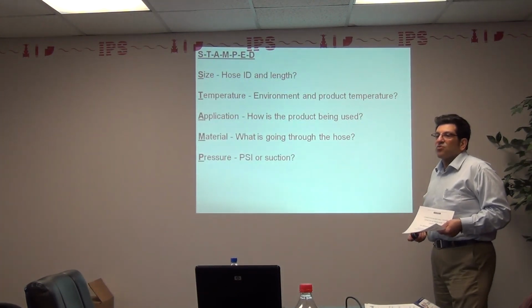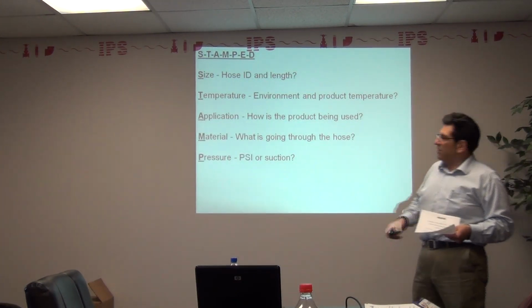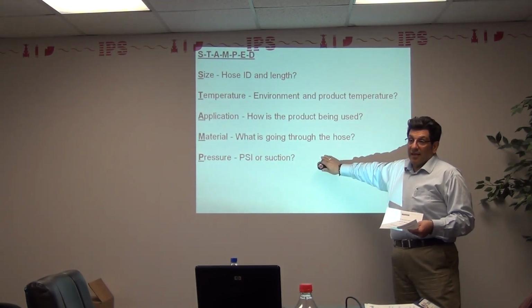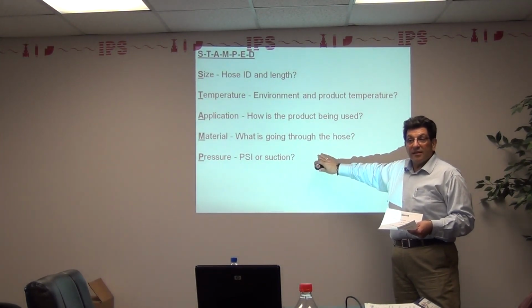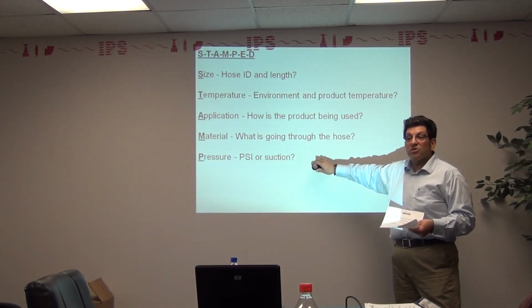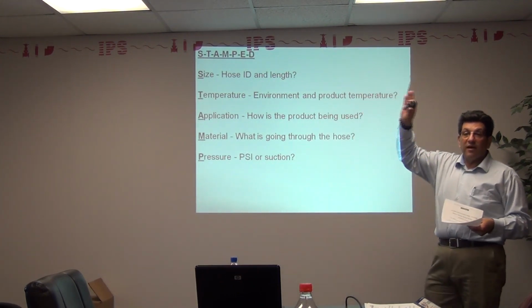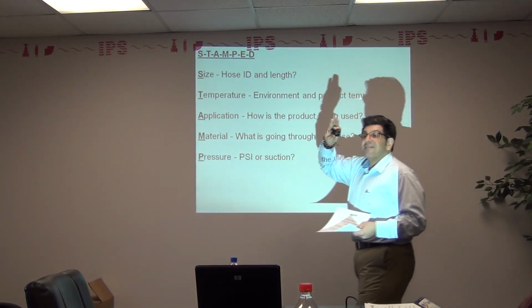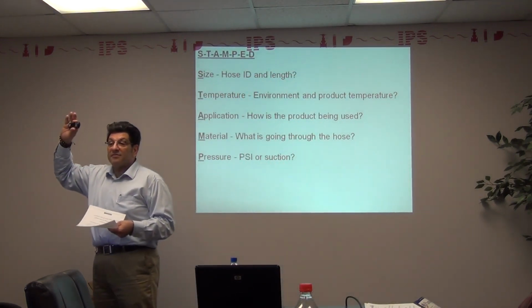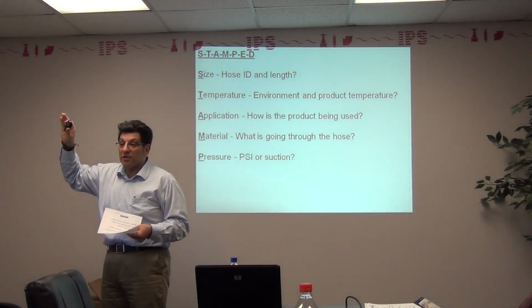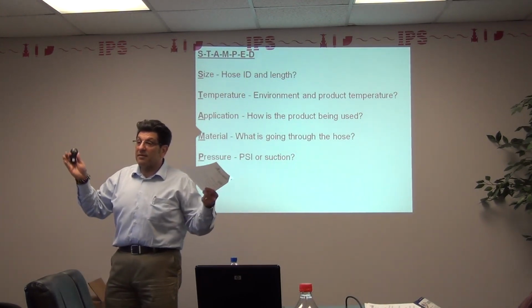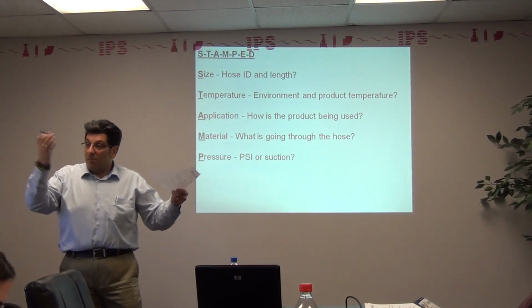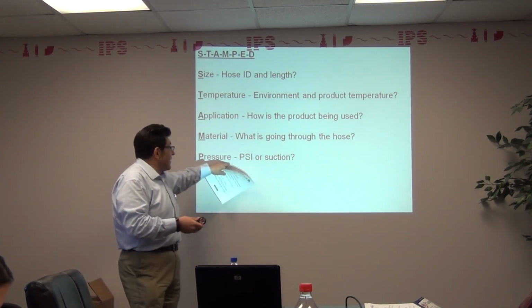Pressure, this is critical, it's critical. The pressure, and then again we want to make sure we qualify the operating pressure, and then what's another important thing to qualify - if they're going to test it. Most typically, a lot of places will test things at 1.5 times its working pressure. So the device may be put out to much more than the operating pressure, so we want to ask.